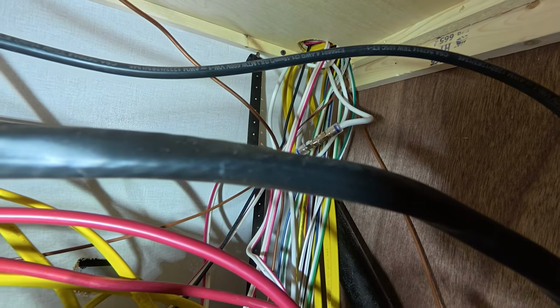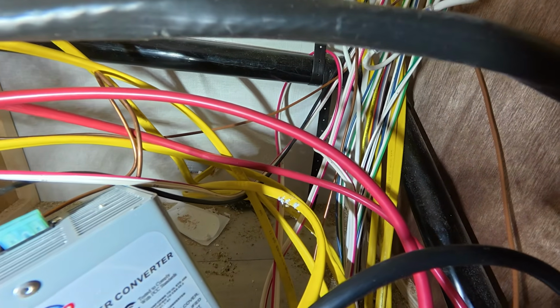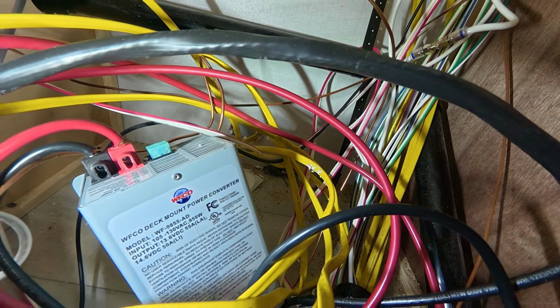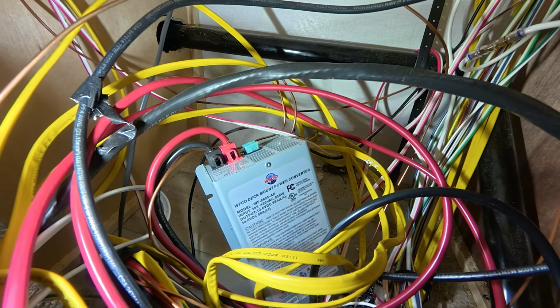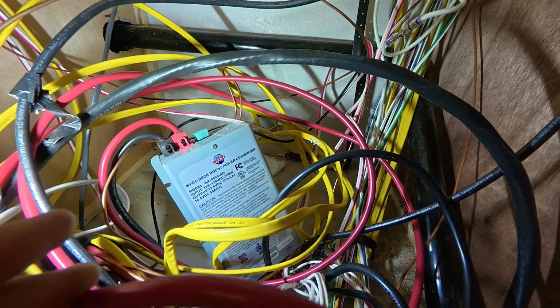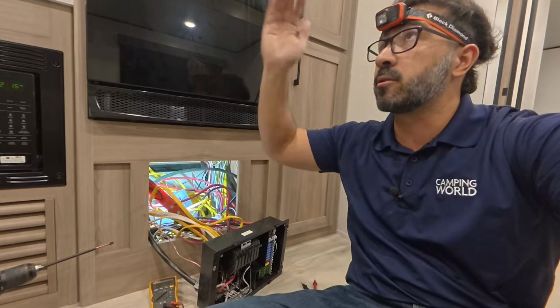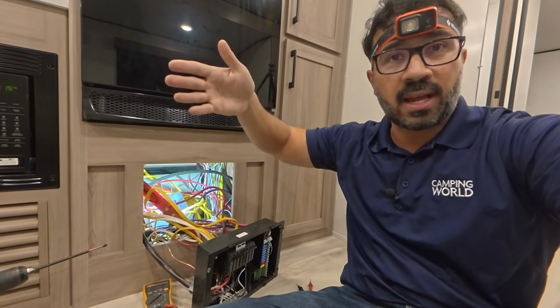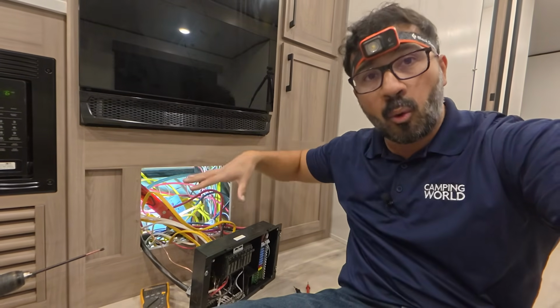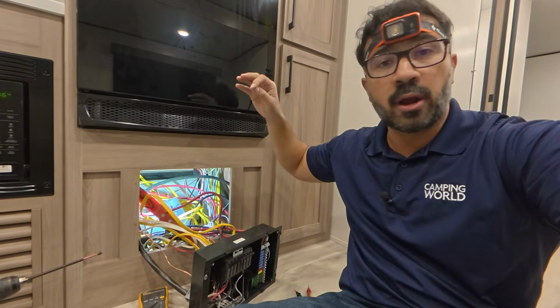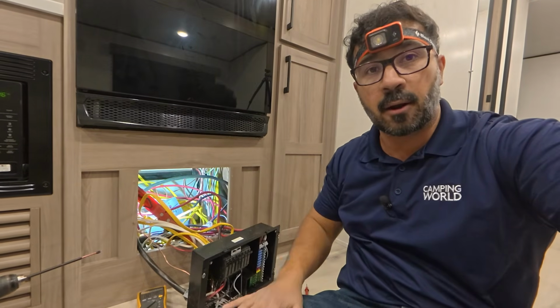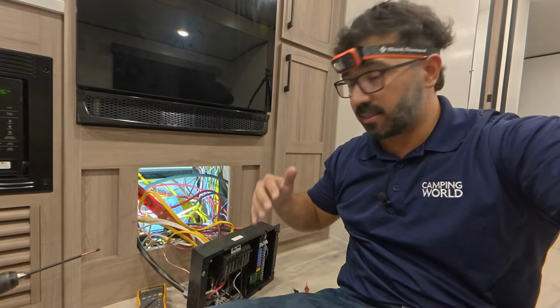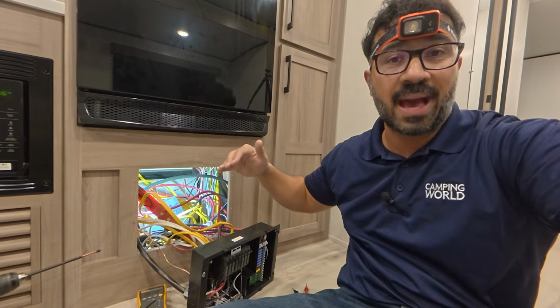While the electrical panel is removed, it's a good idea to visually inspect the wiring. You're looking for signs of melted insulation, corrosion, or loose connections. However, please be extremely careful here. If you notice any issues you want to examine further, make sure you remove power again—you can see I have the lights on, power on. You'll want to kill both AC and DC before you touch any potential live wires, connectors, or terminals in here.